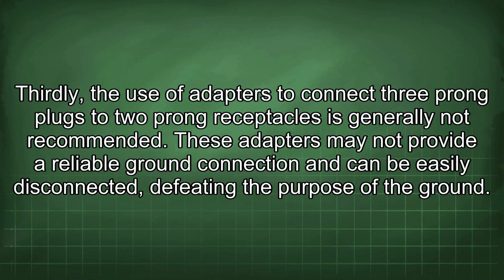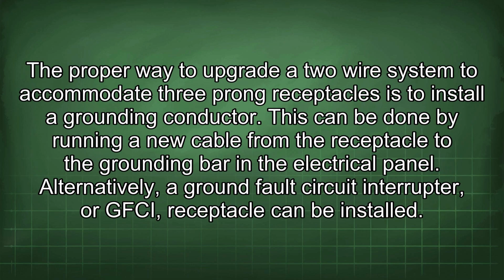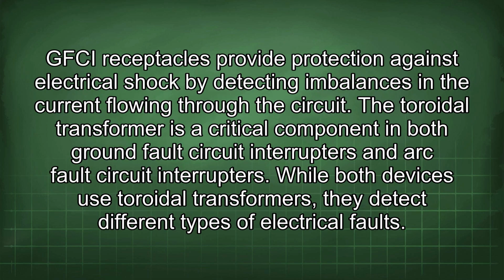Thirdly, the use of adapters to connect three-prong plugs to two-prong receptacles is generally not recommended. These adapters may not provide a reliable ground connection and can be easily disconnected, defeating the purpose of the ground. The proper way to upgrade a two-wire system to accommodate three-prong receptacles is to install a grounding conductor. This can be done by running a new cable from the receptacle to the grounding bar in the electrical panel. Alternatively, a ground fault circuit interrupter, or GFCI, receptacle can be installed. GFCI receptacles provide protection against electrical shock by detecting imbalances in the current flowing through the circuit.